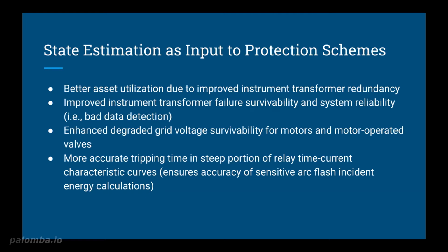Moreover, the NRC likes to cite violations for lack of thermal overload set point testing program, even though there's no industry operating experience to indicate that the set points of these bimetallic contacts drift over time. So a state estimation-based protection could simplify these issues rather than rely on these old-fashioned thermal overload relays. The condition of the insulation in motors can be estimated as a state based on voltage and current draw, which would result in more appropriate protection.